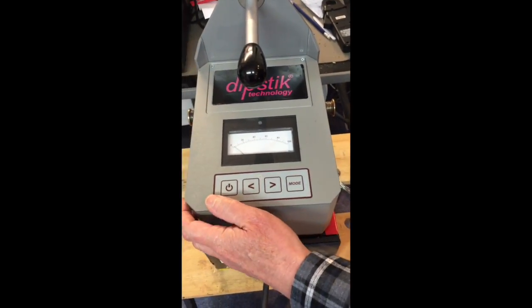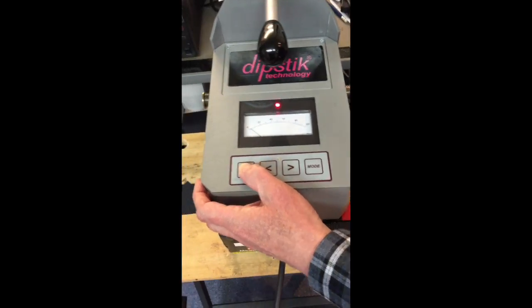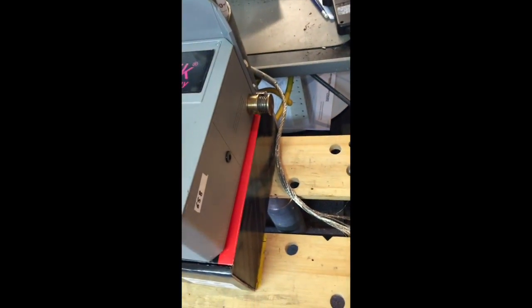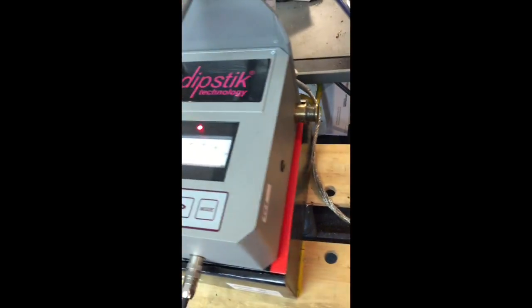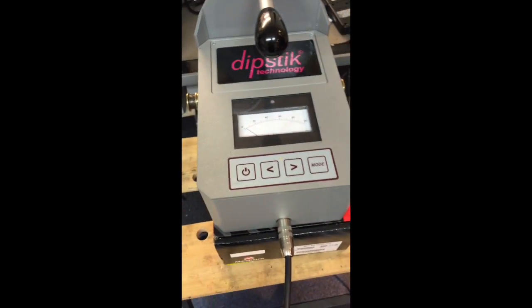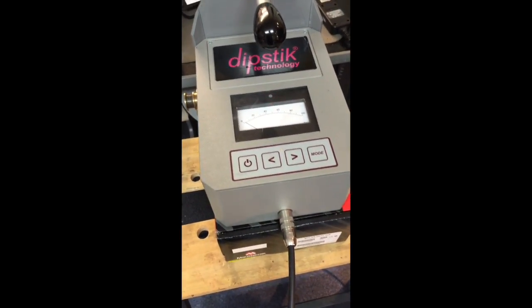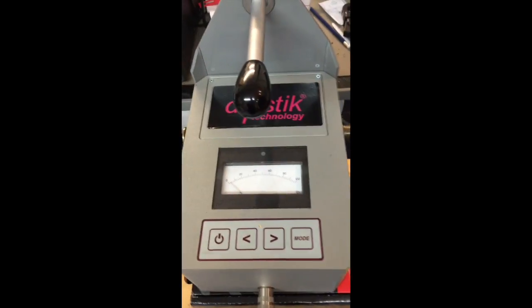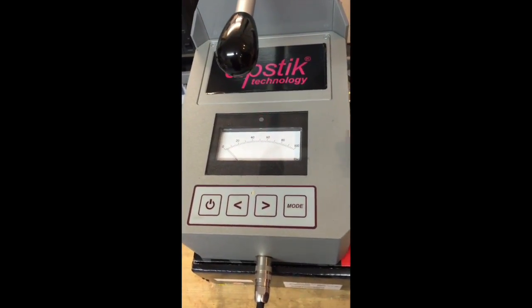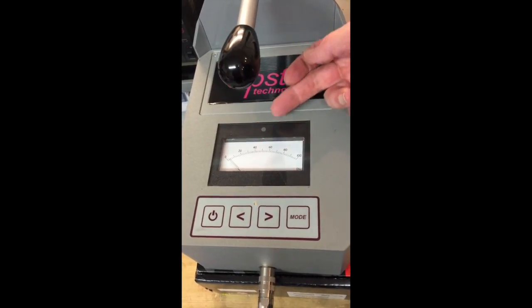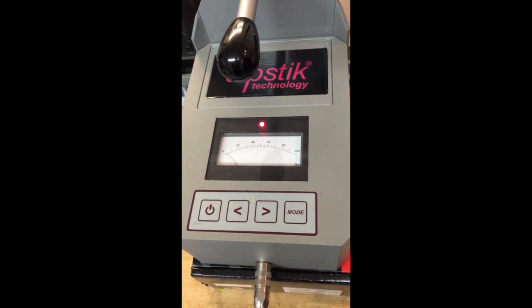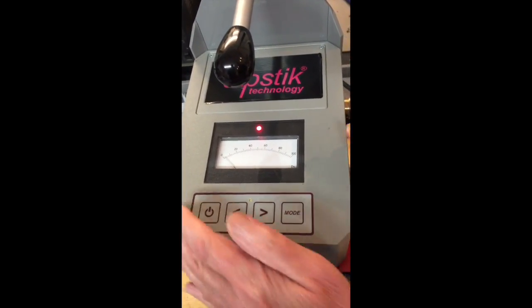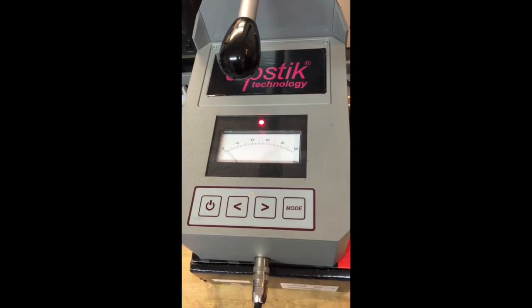We're now going to simulate what happens if you're not picking up a proper signal. We've done this by disconnecting the heavy current coil which goes around the column, but it could also be you may be too far down the column to pick up a proper signal. Right, now here we go. And the meter will probably give a stable reading, but the indication of the LED flashing repeatedly is that the reading on the meter is not valid.